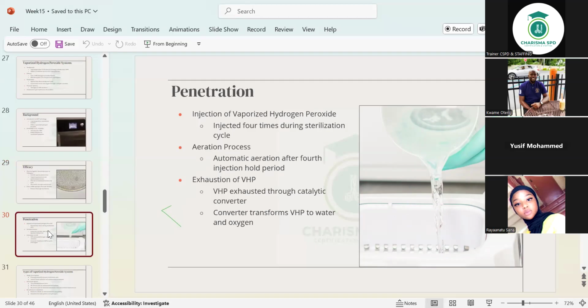The penetration, which is the exposure or the diffusion, okay? The injection of vaporized hydrogen peroxide, it's injected 4 times during sterilization cycle. Aeration process, automatic aeration after the 4th injection. So after the 4th injection, the instruments have had the exposure that they require. So then the machine injects air in there. Okay, the aeration process takes place to get rid of whatever gases are left on there. And that's why I said it's not cold air that comes in; it's warm air that comes in. All right. Okay. So then the exhaust phase comes in, where the VHP system is exhausted through a catalytic converter, turning whatever is in there into water and oxygen, right? Yeah. So the converter transforms the VHP to water and oxygen. That's good news. So nothing bad coming out.